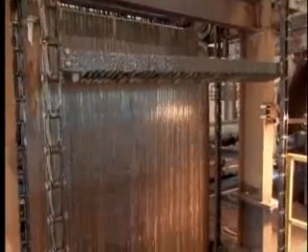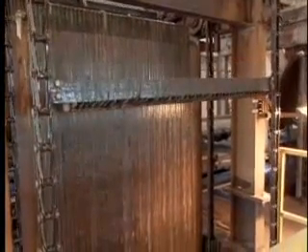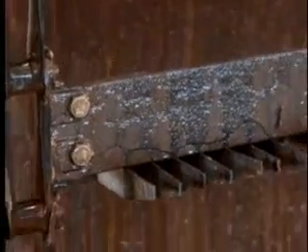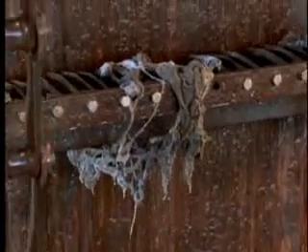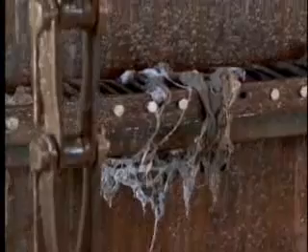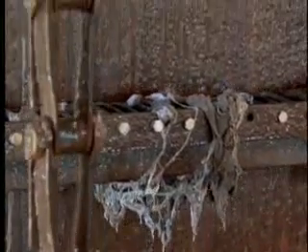One of the first processes in a wastewater plant is a screening process. In a little or a lot, almost everything finds its way into a wastewater plant. This screen has 1-inch openings down at the bottom that will capture any big debris, such as logs or sticks, large rags, anything that would damage equipment downstream. We try to remove in the screening processes.